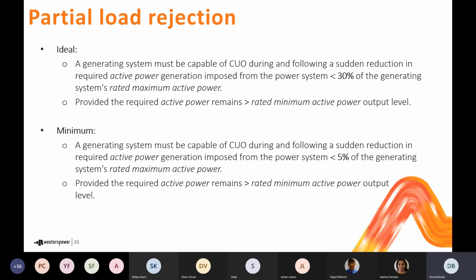So the next one of the disturbance ride-through requirements talks about the ability to respond to a partial load rejection. The ideal standard that's proposed here is very similar to the partial load rejection requirements that exist in the existing technical rules, which also requires the ability to ride through a 30% partial load rejection. The minimum standard provides for a relaxed requirement, requiring you to ride through a 5% partial load rejection.